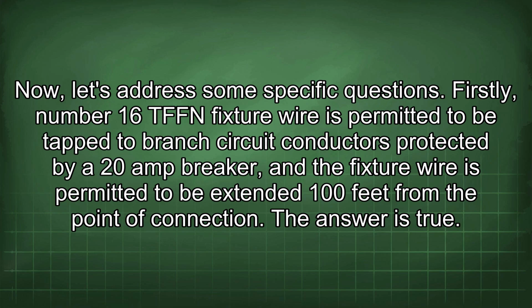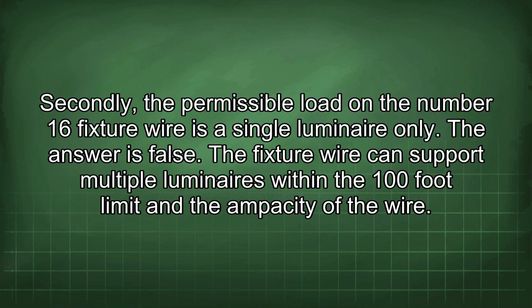Firstly, number 16 TFFN fixture wire is permitted to be tapped to branch circuit conductors protected by a 20-amp breaker, and the fixture wire is permitted to be extended 100 feet from the point of connection. The answer is true. Secondly, the permissible load on the number 16 fixture wire is a single luminaire only. The answer is false. The fixture wire can support multiple luminaires within the 100-foot limit and the ampacity of the wire.